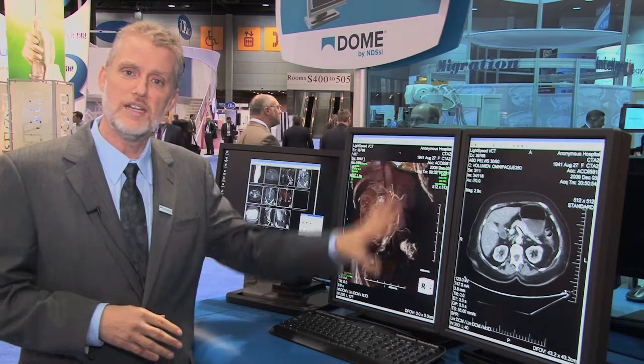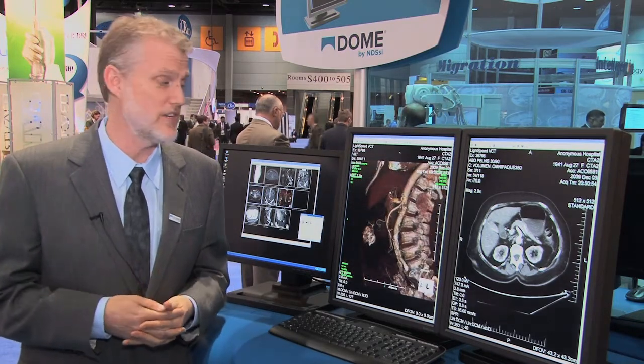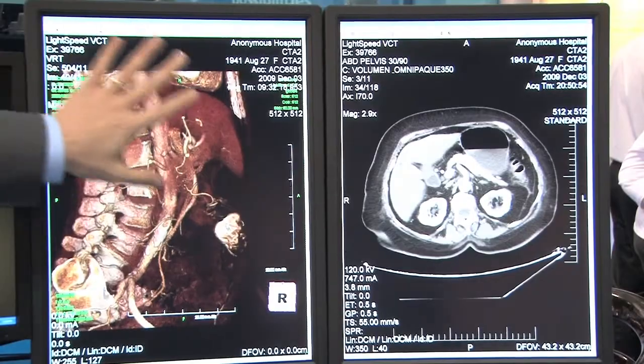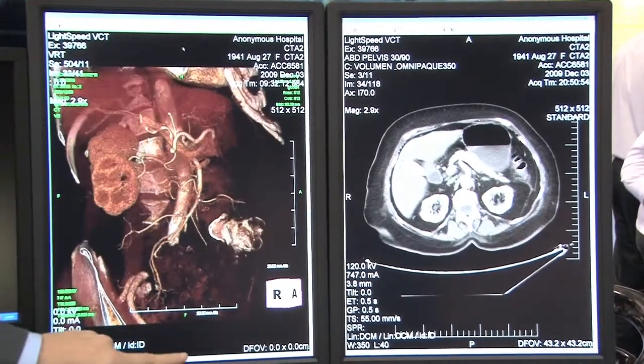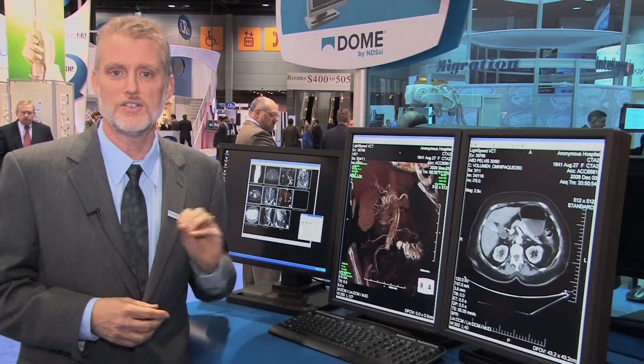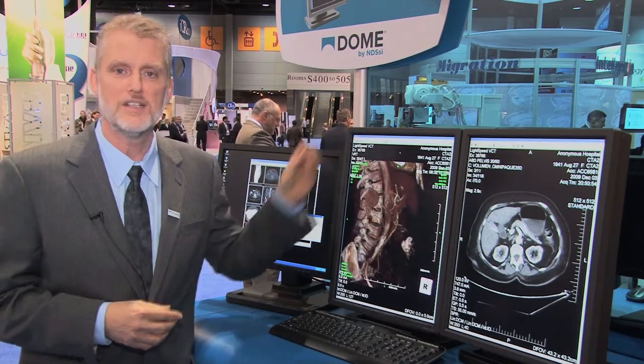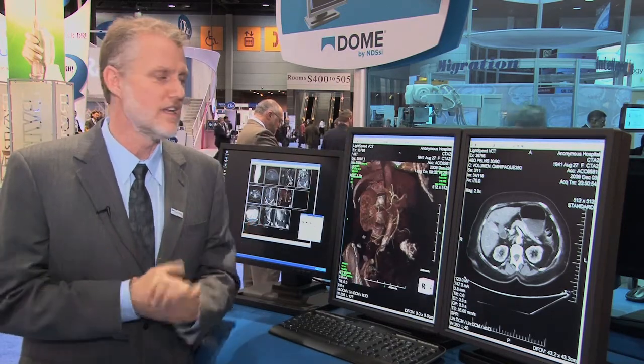We also don't put any reflective glass across the display because we feel that that also is disruptive, and the ACR agrees, recommending against any use of protective glass unless absolutely necessary. This allows us to give you clean displays, clean images, but also clean design. Very efficient, very smooth, no fans, no other noise sources. It's a wonderful display. And I'd like to show you some of our new products.